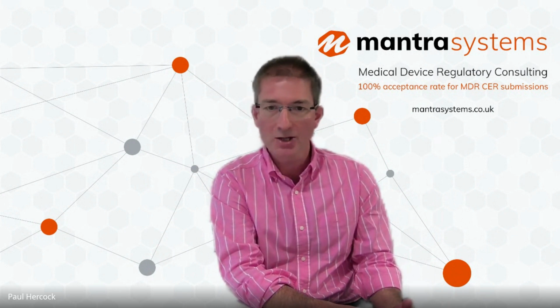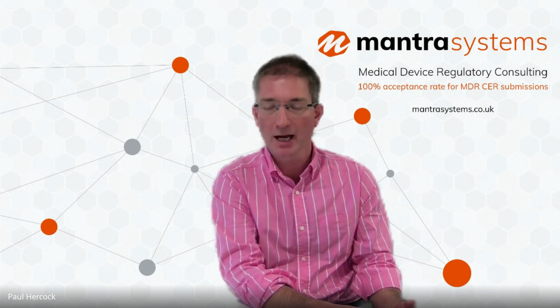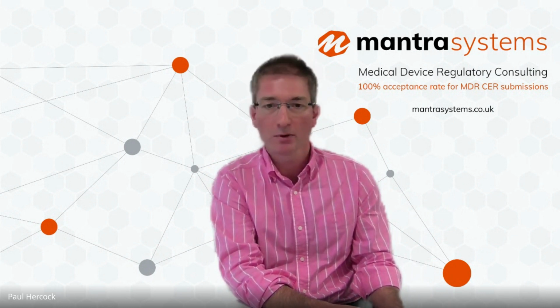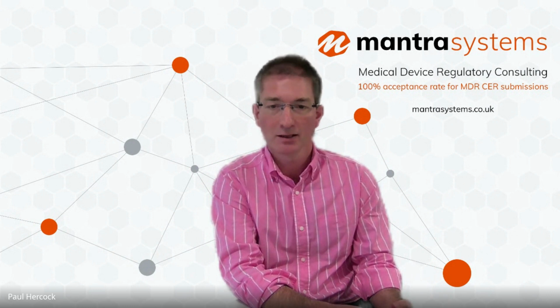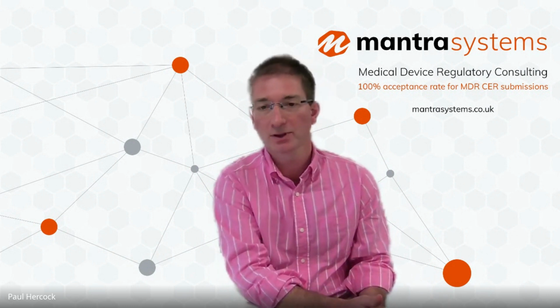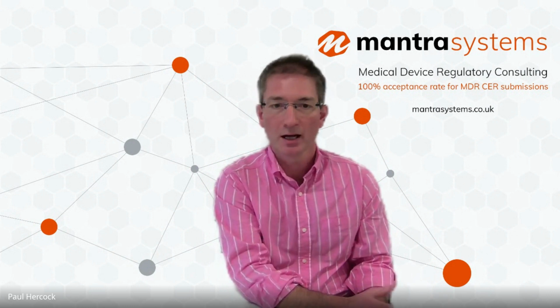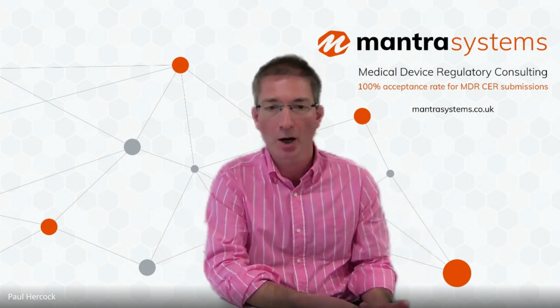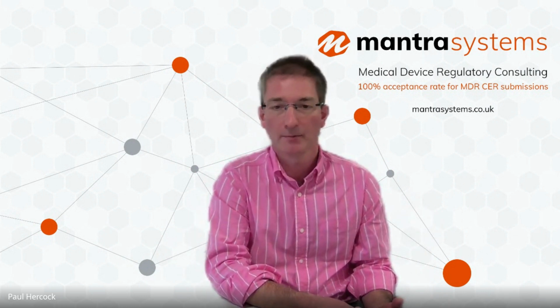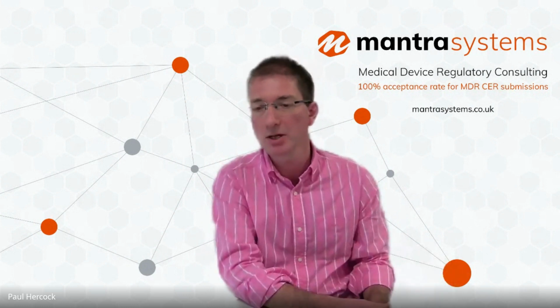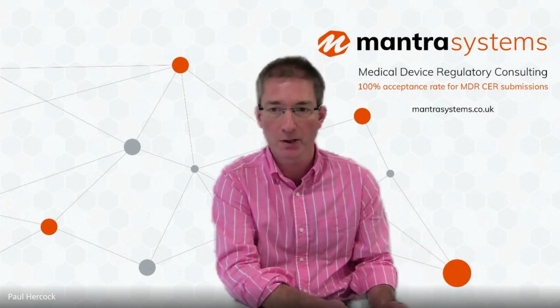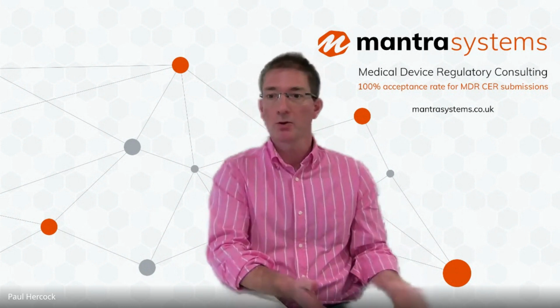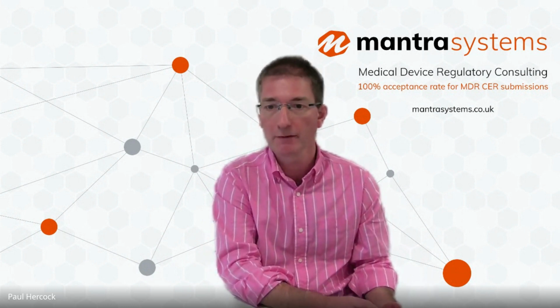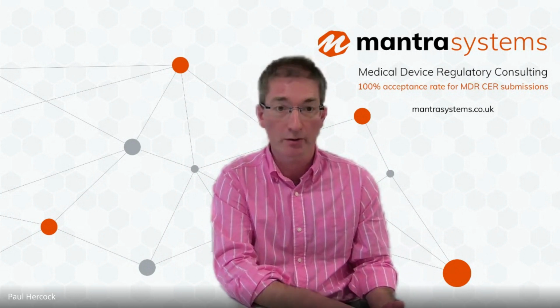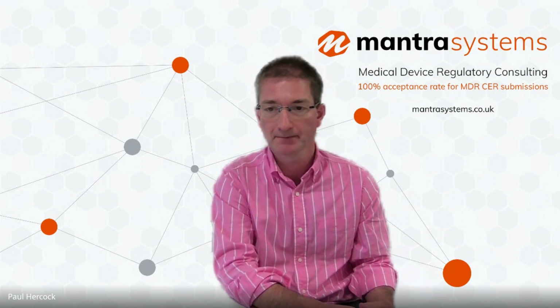There are one or two potential exceptions to that in very, very limited cases. One might be if you're using a software algorithm in an unchanged manner for the same specific purpose as it's been used elsewhere. In theory, given the same input, that can only ever produce the same output. So you may be able to use data related to that algorithm if it's been used elsewhere. But that would pose the question, why not just use an equivalence claim? So fundamentally, it's subject device data or equivalent device data that you need to use.